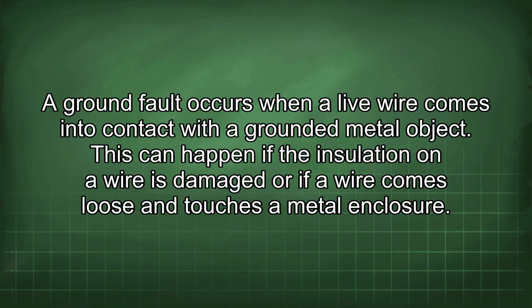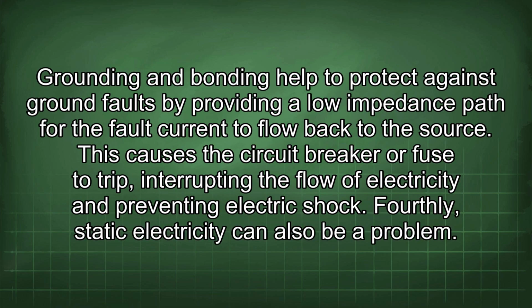A ground fault occurs when a live wire comes into contact with a grounded metal object. This can happen if the insulation on a wire is damaged or if a wire comes loose and touches a metal enclosure. Grounding and bonding help to protect against ground faults by providing a lower impedance path for the fault current to flow back to the source. This causes the circuit breaker or fuse to trip, interrupting the flow of electricity and preventing electric shock.